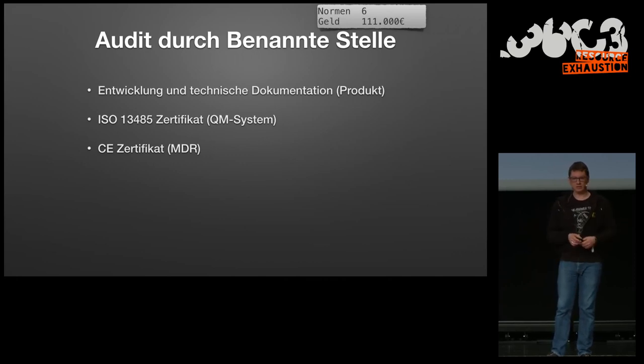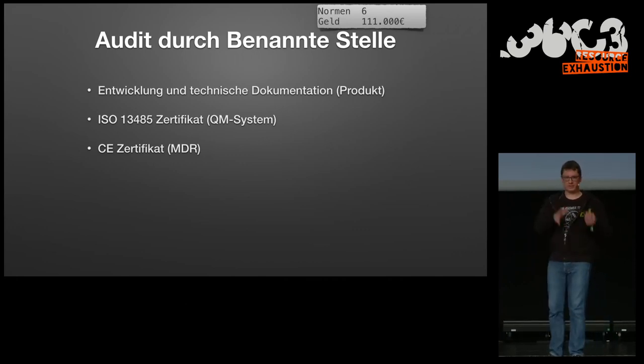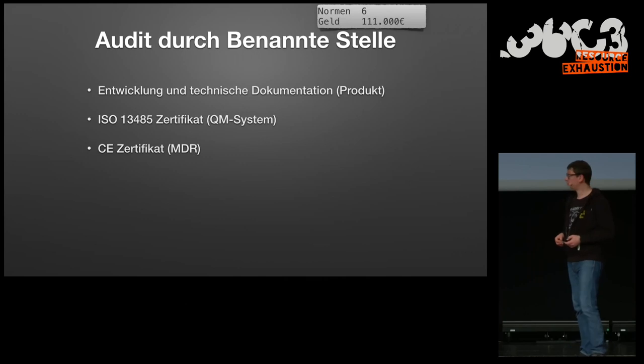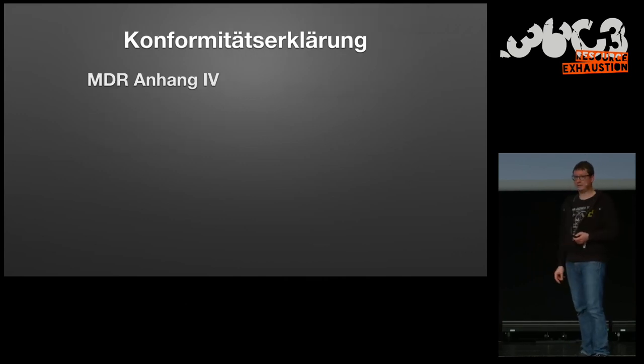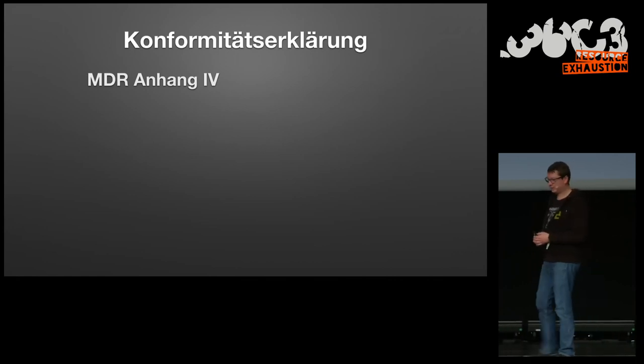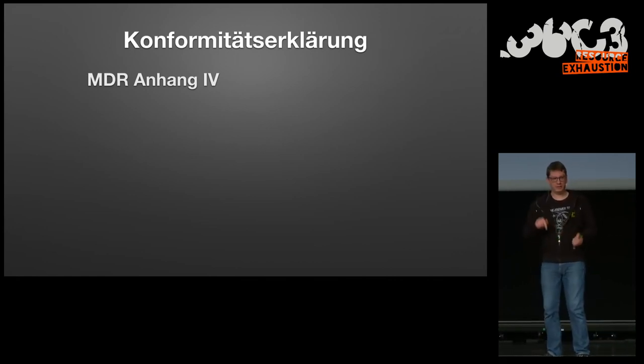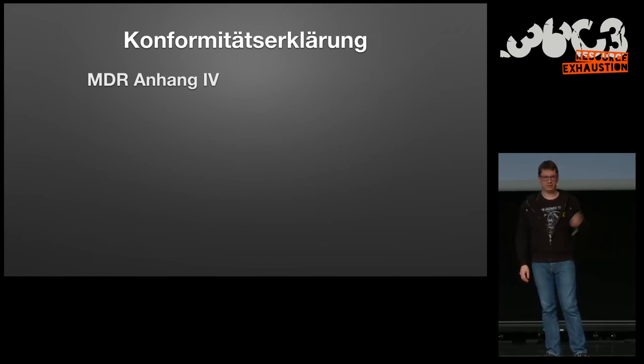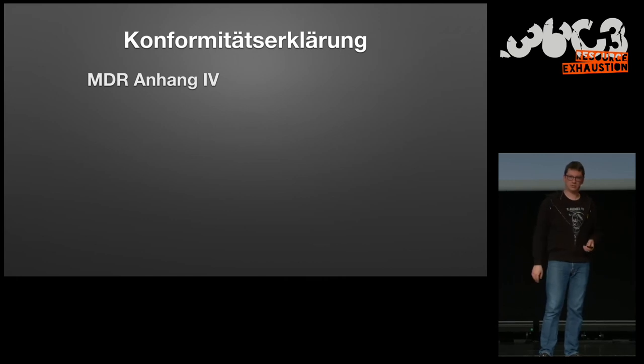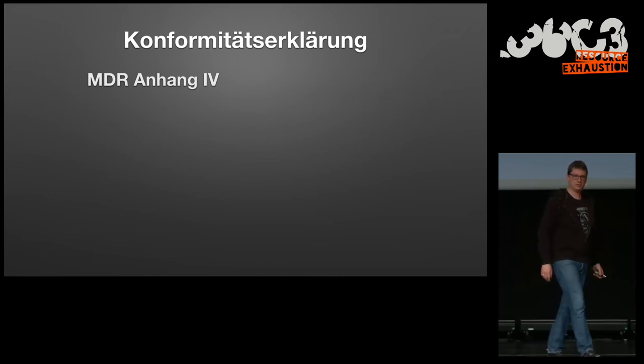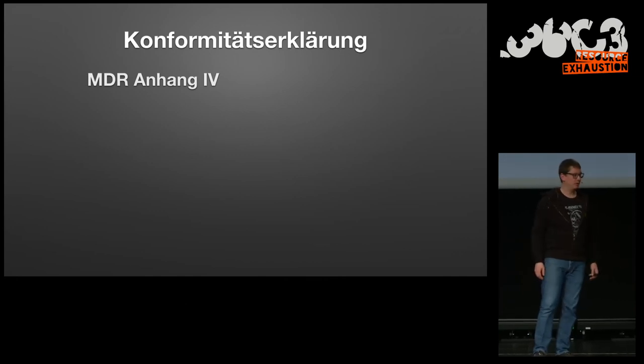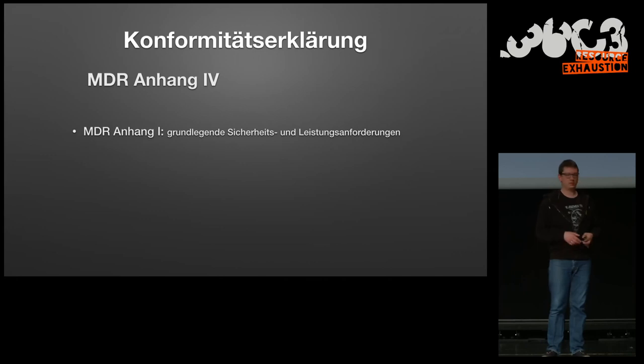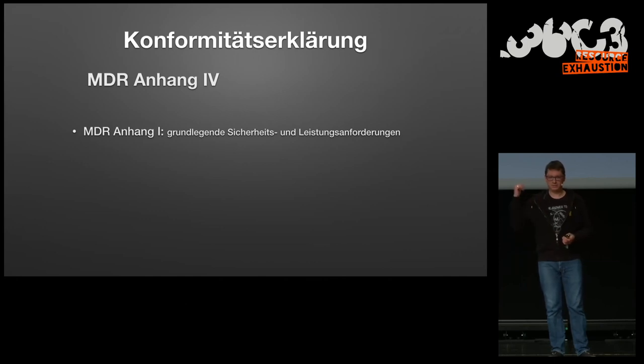Next thing is the audit of the 13485. If you pass, you get a certificate, and then there's another certificate which by law allows you to put certain things on the market. You then declare the conformity. That's very important in the EU. There's no admission by the state. In the US, you go to the FDA and they admit your product, approve your product. In Europe, you do this yourself. This is written in the MDR Annex 4.